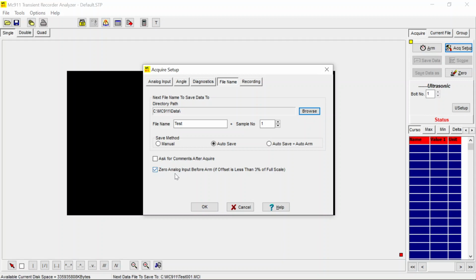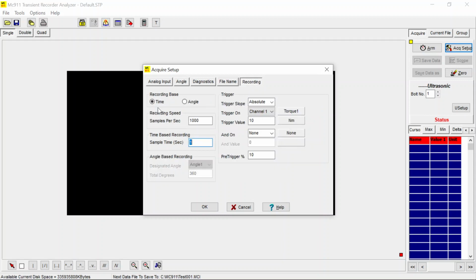Sometimes we don't need this if we are working with very small torque or very small loads, so you need to disable it. But in this case, it's a good idea to have it on. Next is recording. We use time-based recording. It's always a good idea to do time-based recording when you have tension involved, because you might not have any torque and no movement, but you might have some load loss. So it will continuously measure that. Make sure you're on time-based.